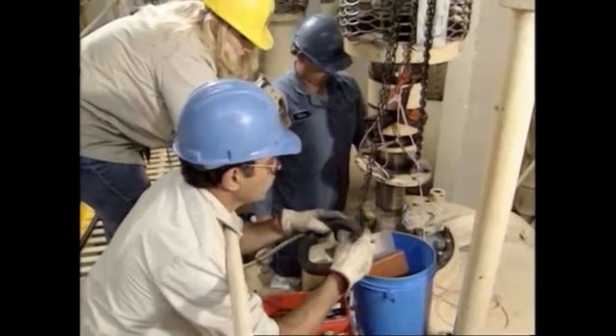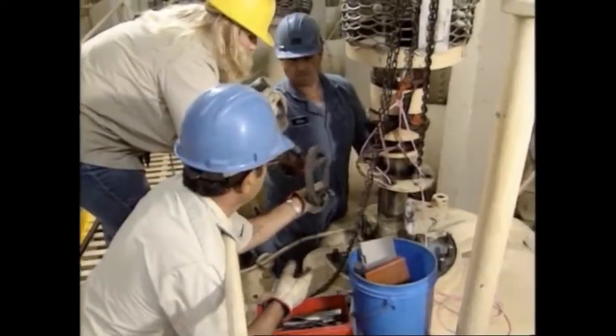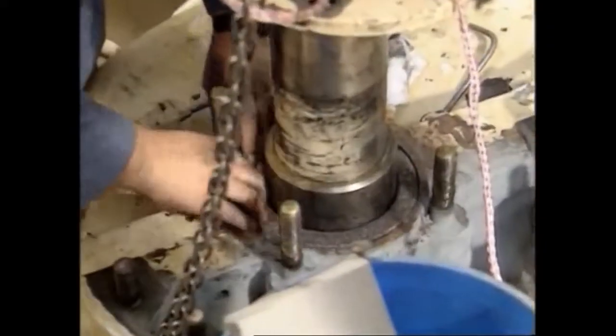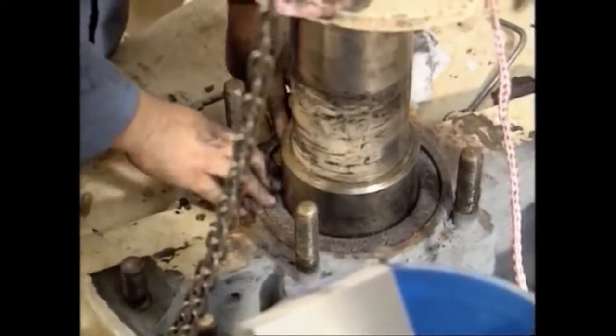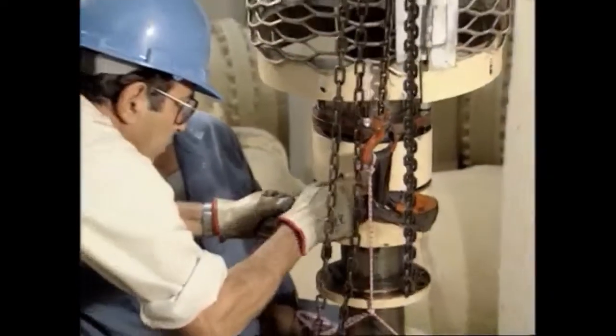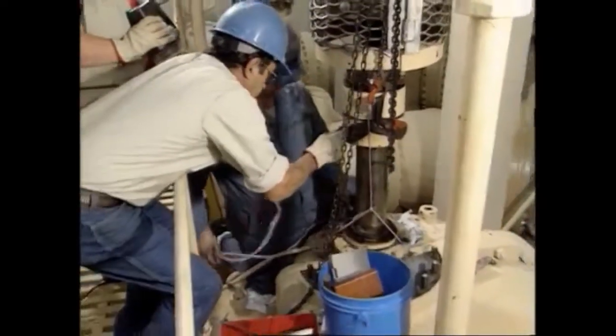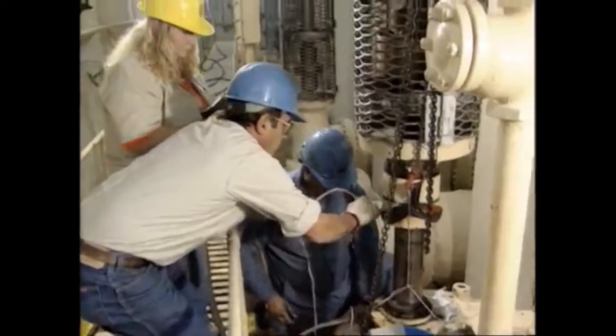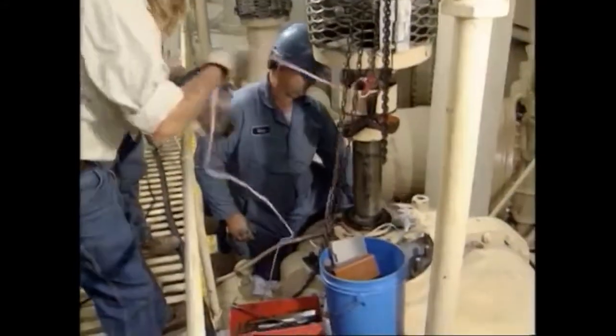Temperature of the liquid being pumped, the grease or water flushing, and the peripheral or outside speed of the shaft are other factors that influence packing. Do not pick a cheap grade of packing. It will cost you more in the end when shaft sleeves are damaged or maintenance time is required to repack. Generally, in wastewater pumps, braided asbestos material is used. It can be graphite impregnated, Teflon coated, or of a similar material.